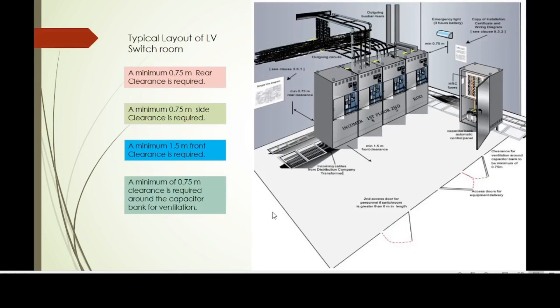Here we have a typical layout of an LV switch room as per ADDC wiring regulations 2020. We need a minimum 0.75 meter rear clearance and 1.5 meter front clearance. Sidewise, we need a minimum 0.75 meter clearance for the LV switchgear, and around the capacitor bank we need 0.75 meter clearance for ventilation.